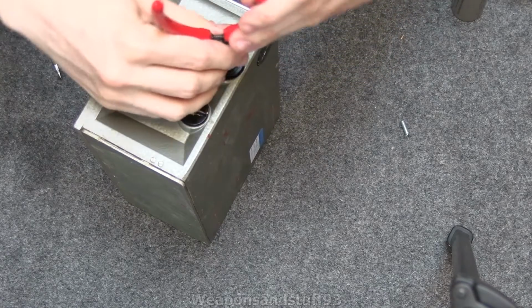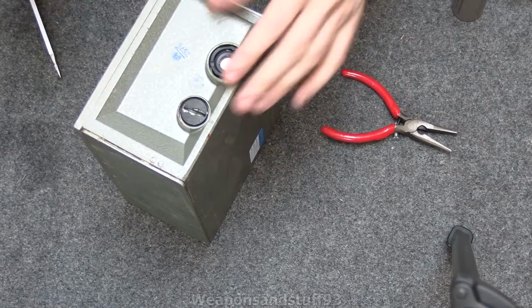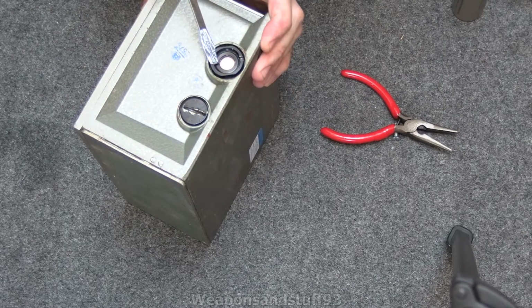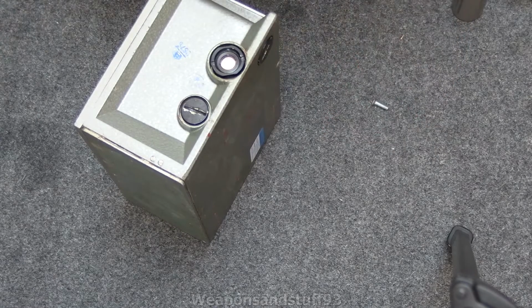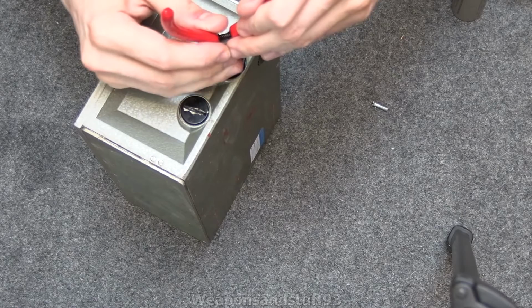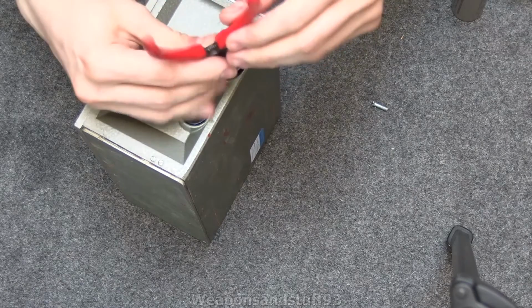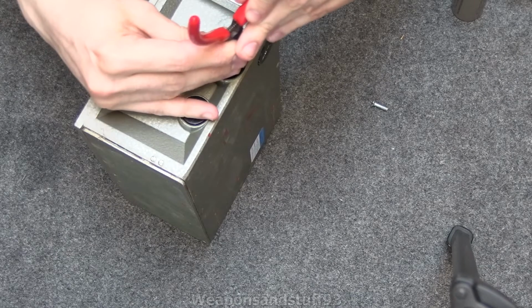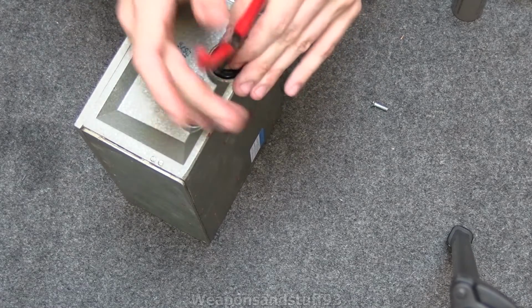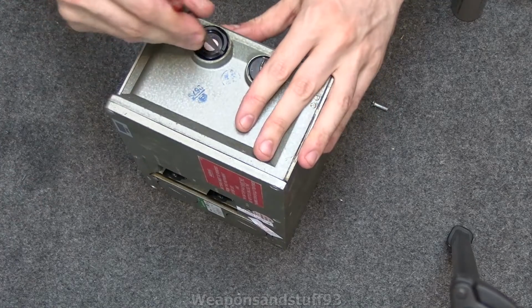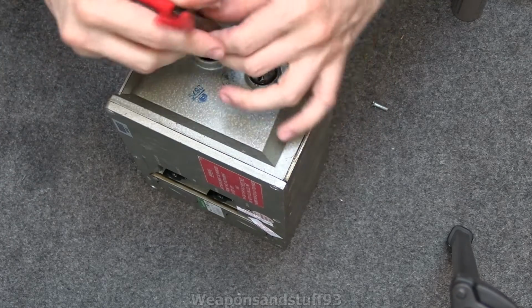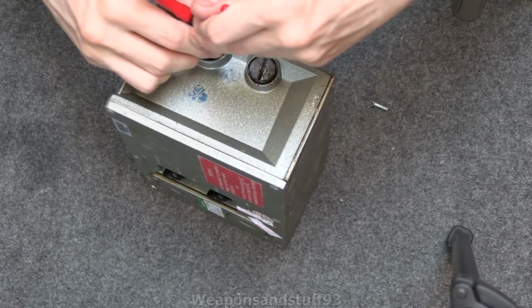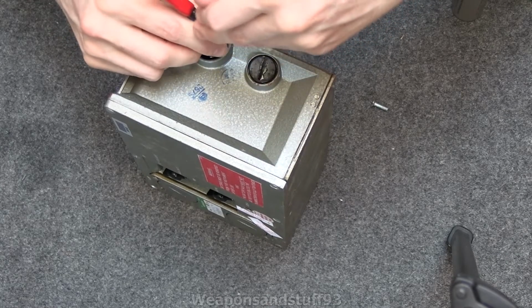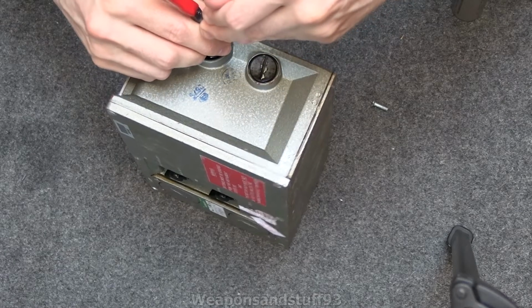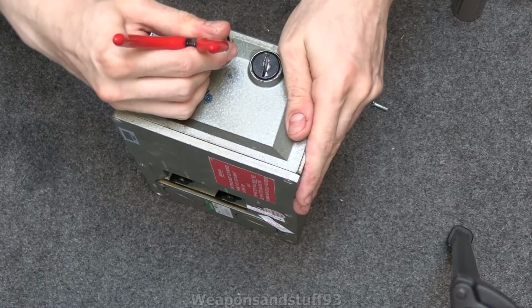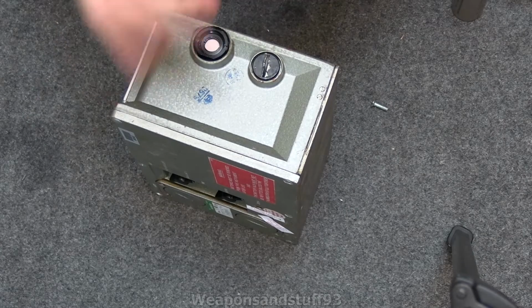So there we go. This is going to be the silica gel cartridge that these would have originally come with. That's actually still not wanting to move all that easily. Yeah, that's still quite solid, so this is why you need pliers for this. So this contains the original silica gel cartridge. Now the issue is, with ionisation chambers, moisture in there gives artificially high readings because moisture is conductive. So the idea with old ionisation chambers was that you would use a bit of silica gel or something similar to keep the inside as dry as possible. Now the issue, obviously, is when you're buying a second-hand meter that's not been used in like 20 odd years, these are going to be well expired.